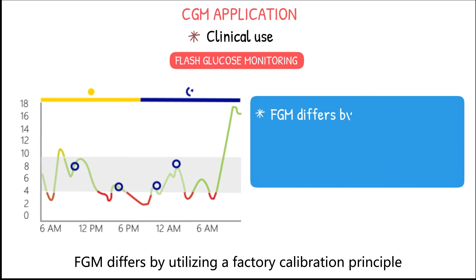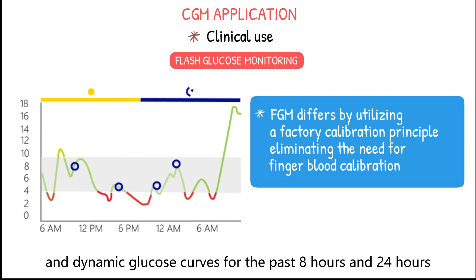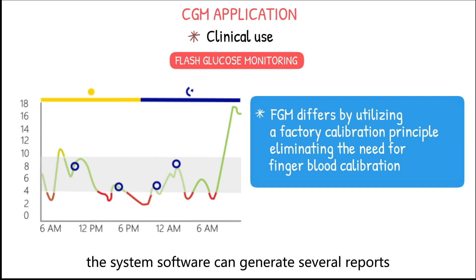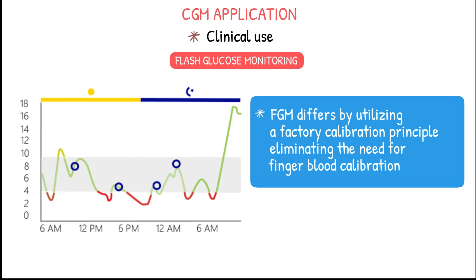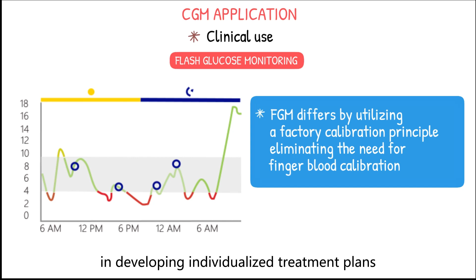FGM differs by utilizing a factory calibration principle, eliminating the need for finger blood calibration. By swiping the scanning detector over the sensor, users can obtain current glucose data, glucose trends, and dynamic glucose curves for the past 8 hours and 24 hours. After downloading the monitoring data, which requires at least 5 days of data for analysis, the system software can generate several reports, including daily glucose result summaries and glucose fluctuation trends. These reports provide valuable reference for clinicians in developing individualized treatment plans.